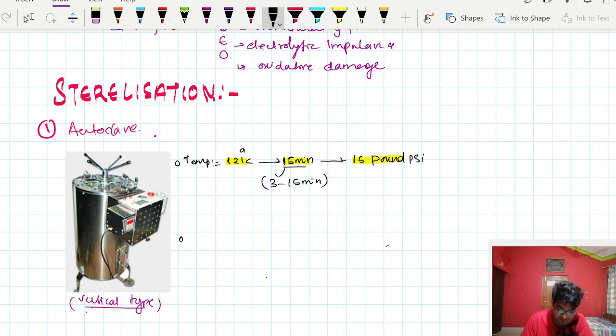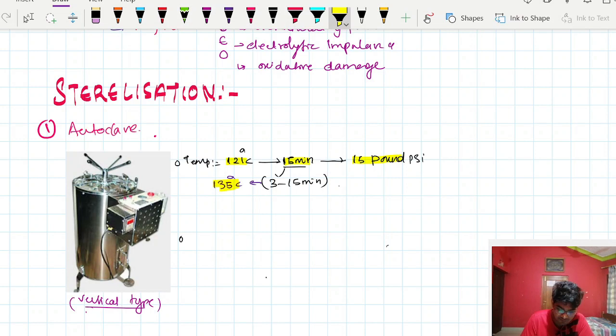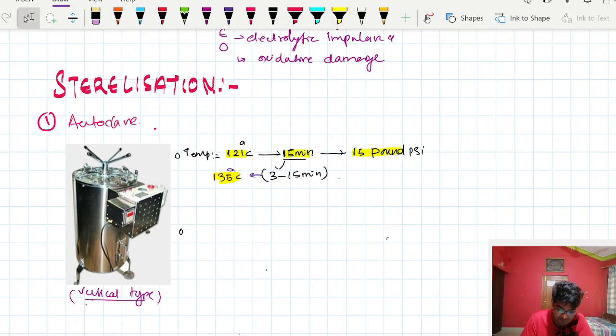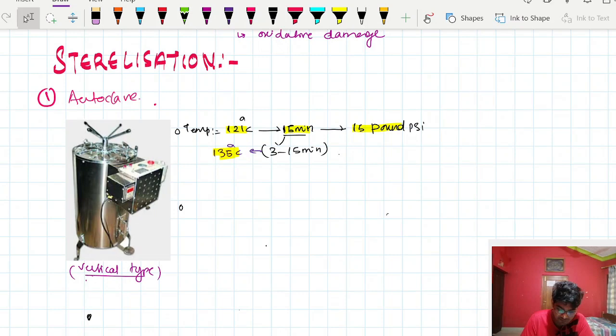If we use 121 degrees Celsius, we keep it for 15 minutes. If we keep it for only 3 minutes, then the temperature must be raised to about 135 degrees Celsius. So we can use temperatures between 121 and 135 degrees Celsius and adjust the time accordingly.